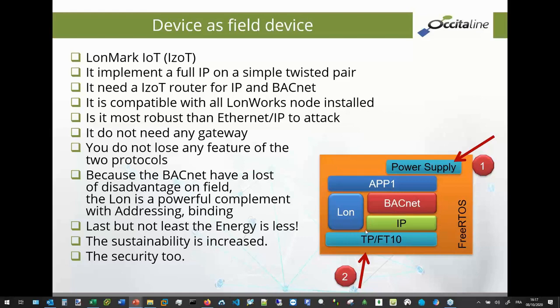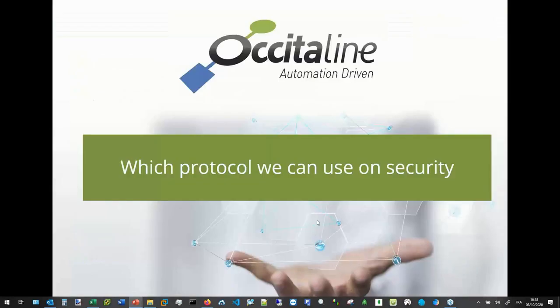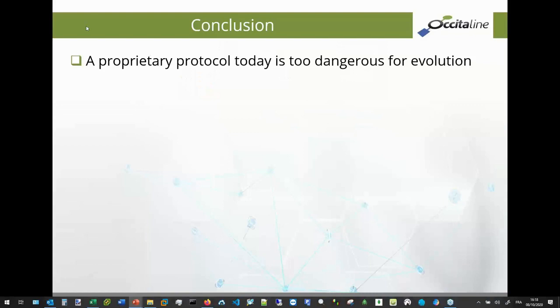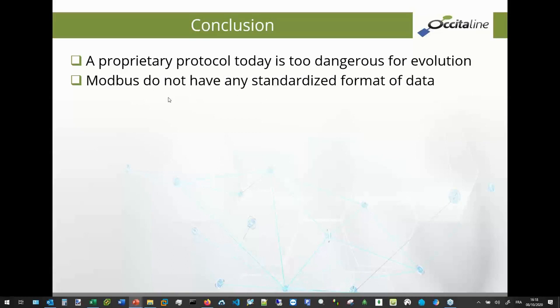To communicate with LON and BACnet, you do not need any gateway. Why? Because a manufacturer can create a data point in LON and a data point in BACnet. And in this case, you do not lose anything about each protocol. Why is it very interesting to have these two protocols on the same device? Because you save energy: the CPU consumes 5 times less, and the transceiver 20 times less, between the Ethernet connection and the TP/FT-10. And the security is also the same as in the small devices not on Ethernet.